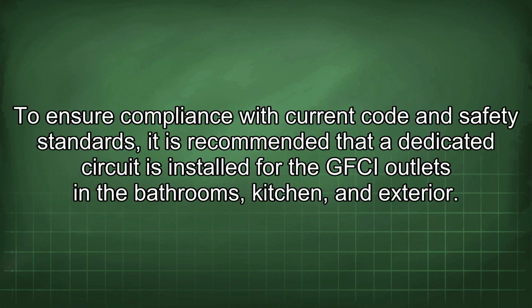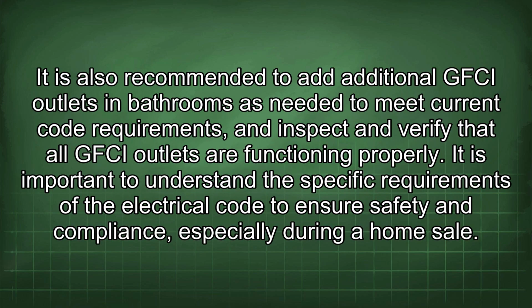code. To ensure compliance with current code and safety standards, it is recommended that a dedicated circuit is installed for the GFCI outlets in the bathrooms, kitchen, and exterior. It is also recommended to add additional GFCI outlets in bathrooms as needed to meet current code requirements, and to inspect and verify that all GFCI outlets are functioning properly.